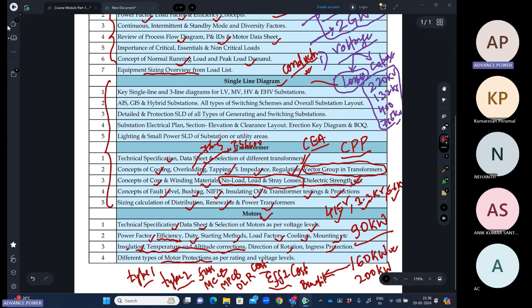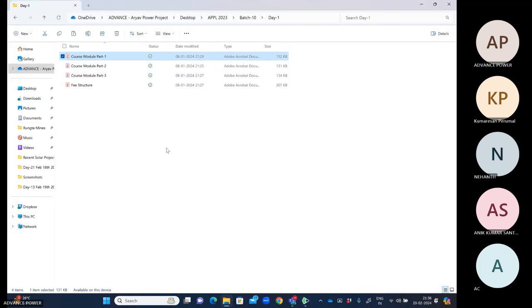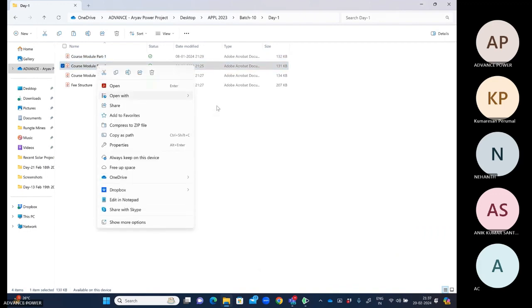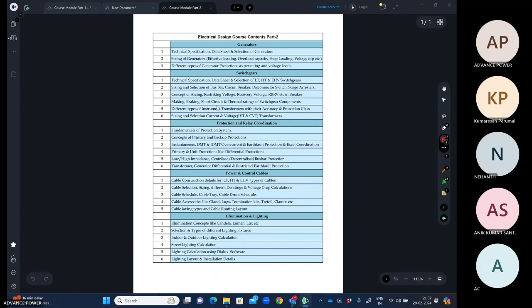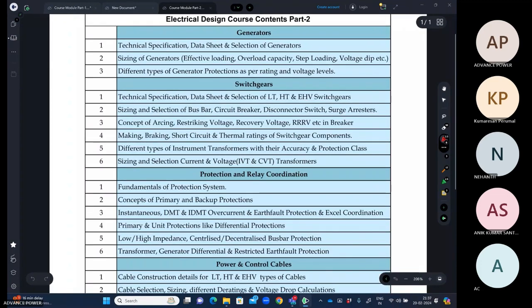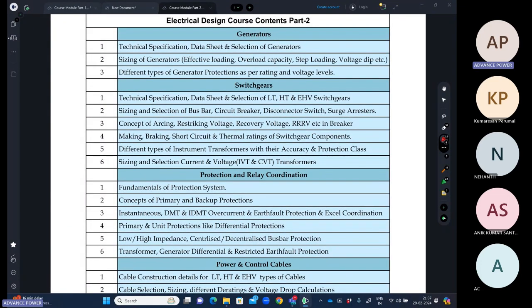After this, we'll go to the generators. We'll do sizing of generators. What is the concept of effective loading, overload capacity, step loading, voltage dip etc. will be evaluated during the generator sizing, and generator protection which will be used, we'll discuss in detail.